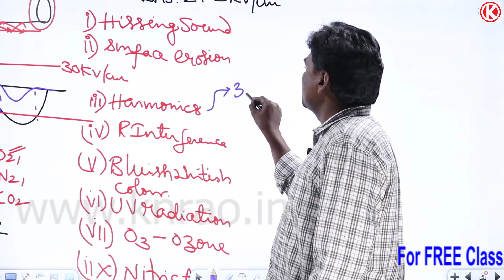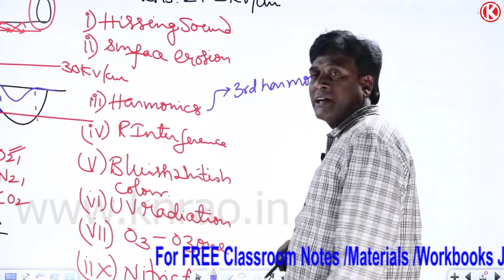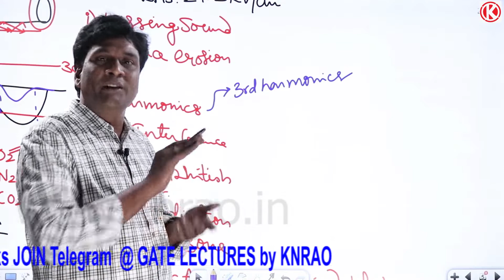Now if you think of harmonics, triplen harmonics is the problem. If you want to know more about this directly, kindly watch the videos on transformers, three-phase transformers, we analyzed harmonics there. Basically the triplen harmonic component of each phase will be in line.